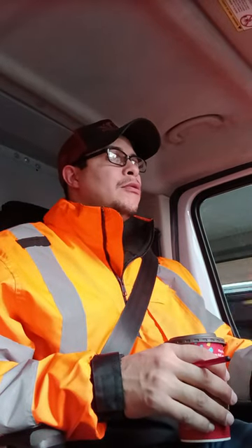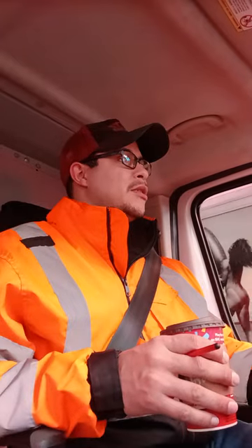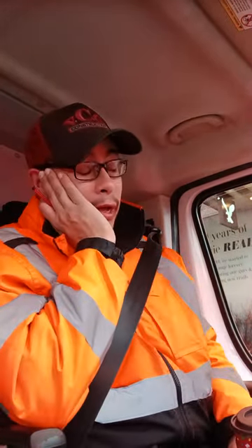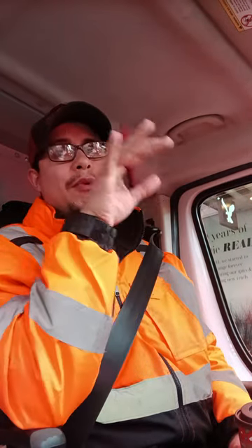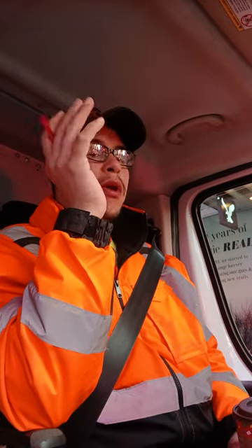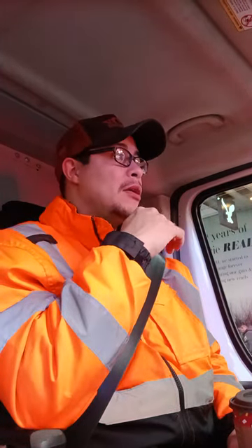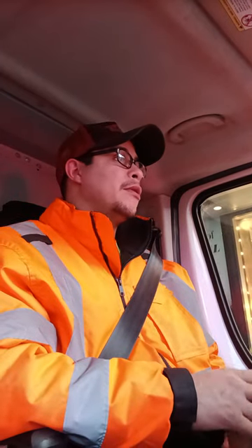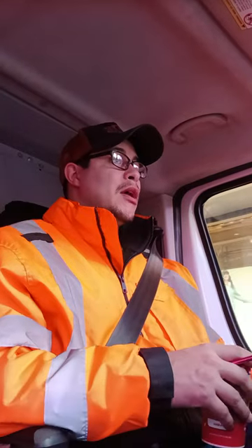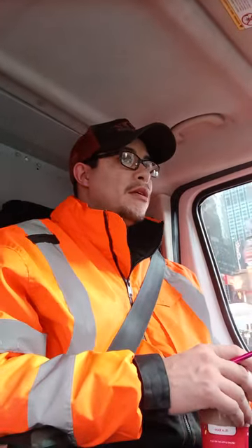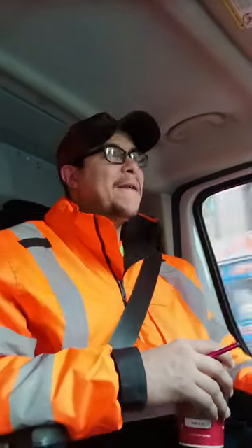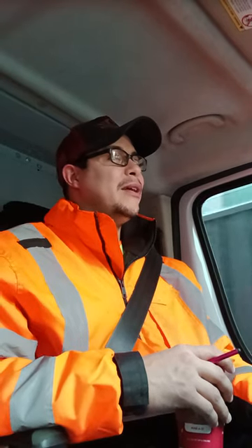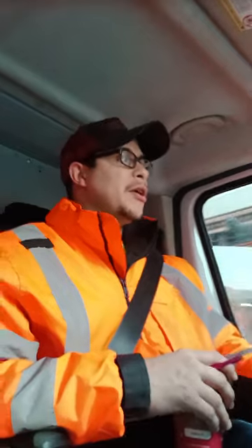But yeah, when it comes down to the kitchen, and I learned this because a lot of inspectors don't realize that the kitchen sink is on one side of the kitchen, and all the way down the line there's no GFCIs because they're away from the sink. So just to keep them happy, I put GFCI breakers on that side of the kitchen counter, and the rest are just regular GFCIs on a regular circuit breaker. They get real antsy about that for some reason, and they totally forget that that counter, which is way away from the sink, where there's no water present, is on a GFCI circuit. I don't think you necessarily have to put a GFCI circuit breaker, but I just do it to keep them happy.